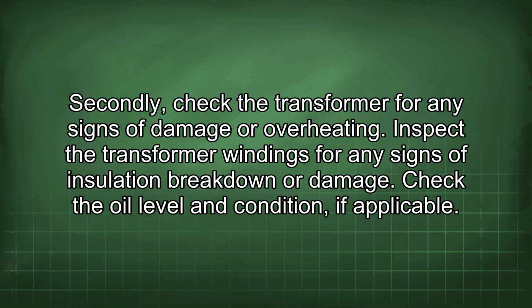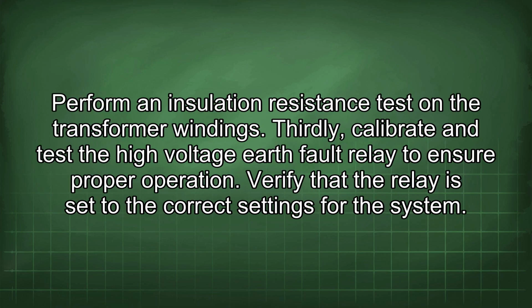Secondly, check the transformer for any signs of damage or overheating. Inspect the transformer windings for any signs of insulation breakdown or damage. Check the oil level and condition, if applicable. Perform an insulation resistance test on the transformer windings.